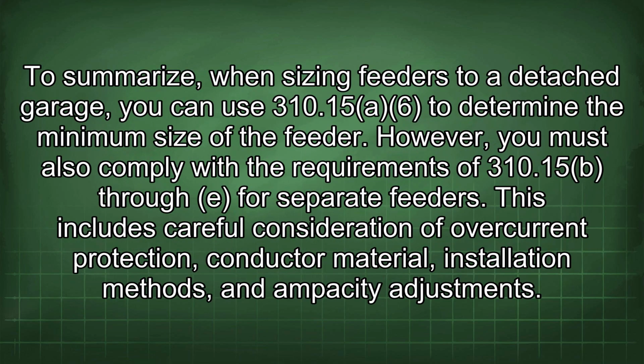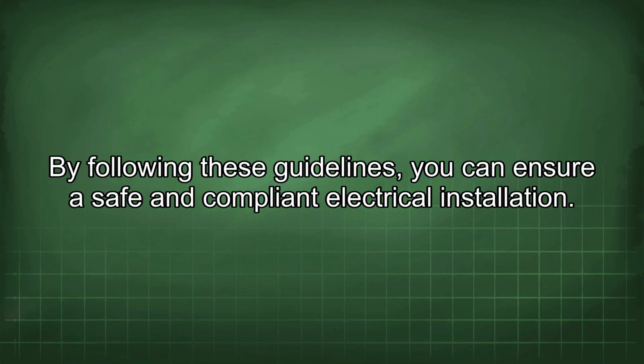To summarize, when sizing feeders to a detached garage, you can use 310.15(A)(6) to determine the minimum size of the feeder. However, you must also comply with the requirements of 310.15(B) through (E) for separate feeders. This includes careful consideration of overcurrent protection, conductor material, installation methods, and ampacity adjustments. By following these guidelines, you can ensure a safe and compliant electrical installation.